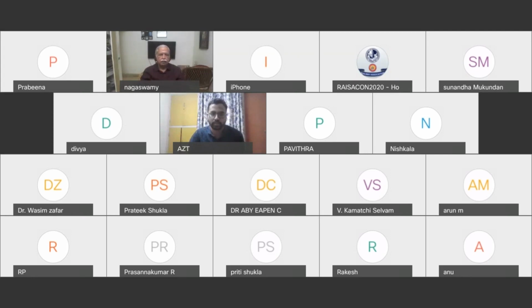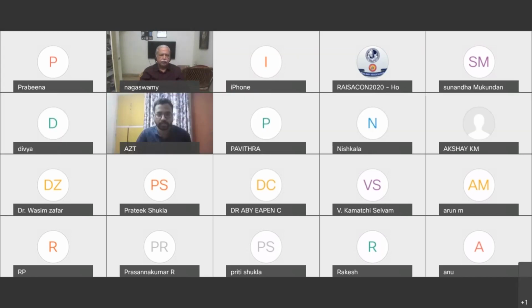Okay, that is the difference between MRI safe and MRI compatible, which is commonly asked in your viva exams. When they talk about MRI, the examiners may ask you, what is the difference between MRI safe and MRI compatible? MRI safe is an equipment which will not be attracted by the magnetic field and fly off, like ferromagnetic objects, implants, and other things. But for the functioning of that equipment, for example a monitoring equipment, you cannot guarantee that it will function properly. Even a pulse oximeter which is not MRI compatible may not read correctly if you take it inside the room. Whereas MRI compatible equipment is safer to take inside, and its function is guaranteed. That is the difference you have to mention.